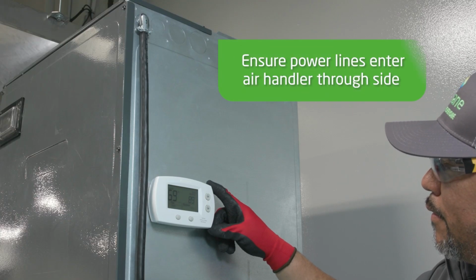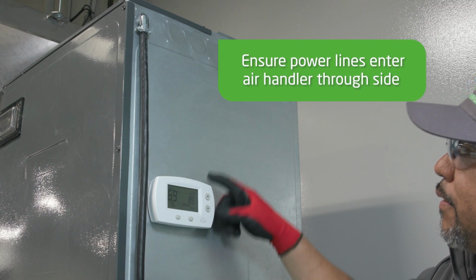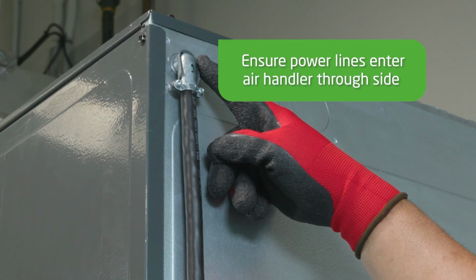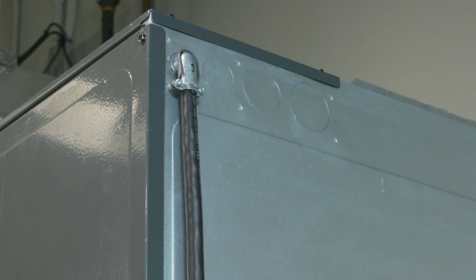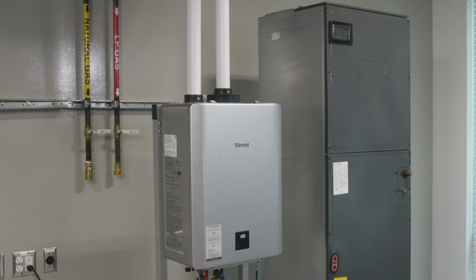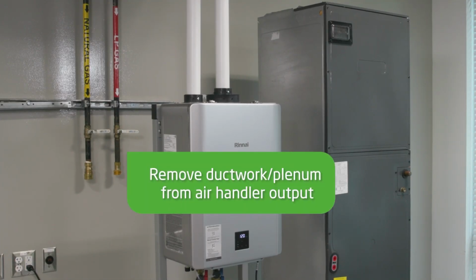Ensure that the primary power and low voltage lines are entering the air handler enclosure through its side and not the top or bottom of the unit. Remove existing ductwork or plenum attached to the outlet of the air handler.